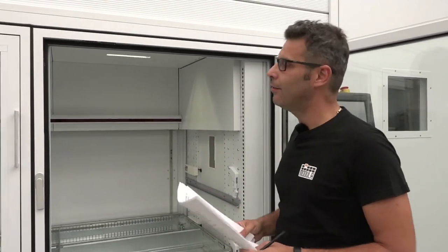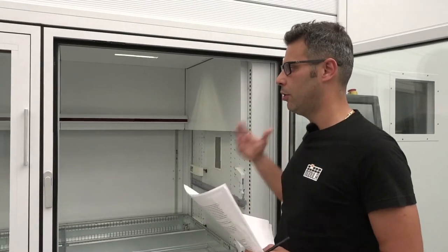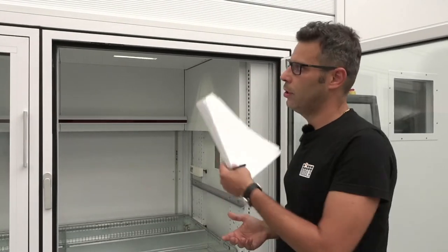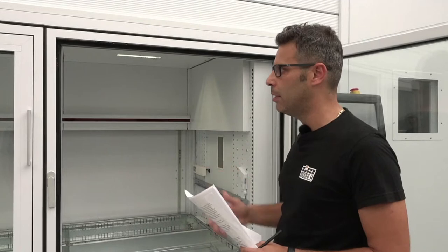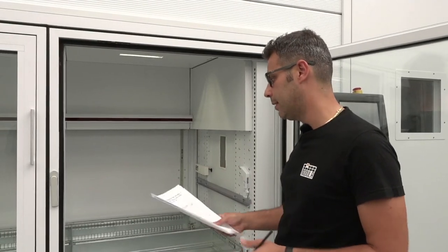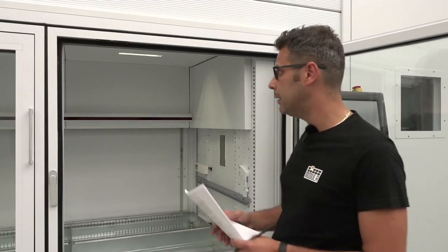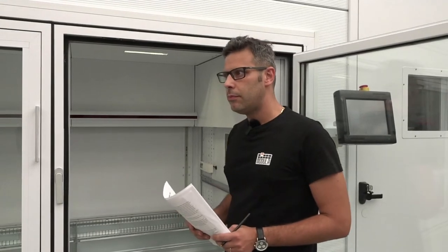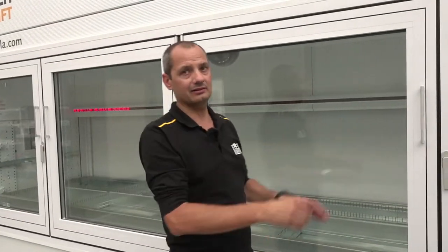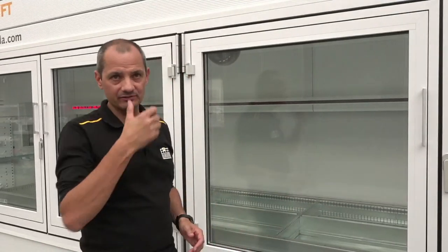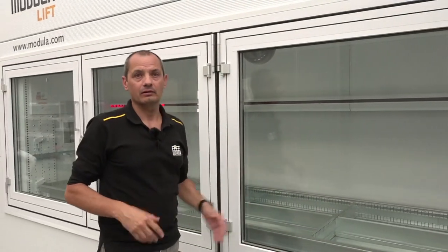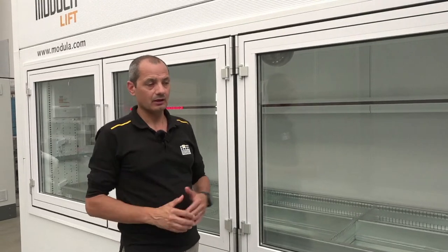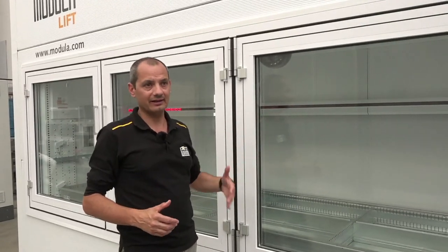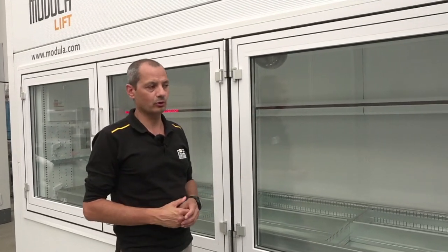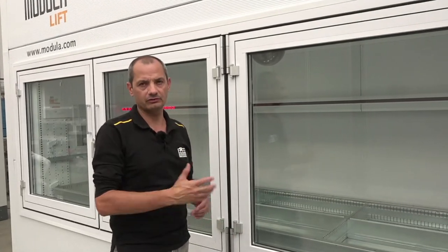We have to remember, otherwise there is a sort of advice, an alarm that warns that the door has remained open. It's good to say that we control both the temperature inside the bay and inside the machine, so if the temperature inside the bay gets too high, for example, the machine itself prevents the tray from coming in. So it's important that you pick and then close the door in a few seconds.